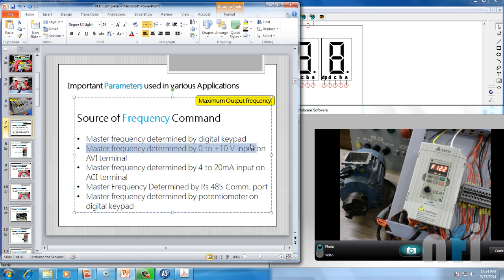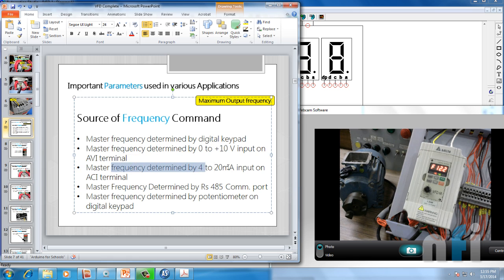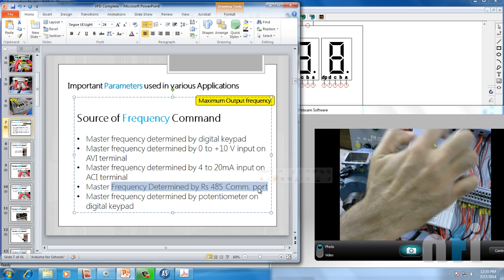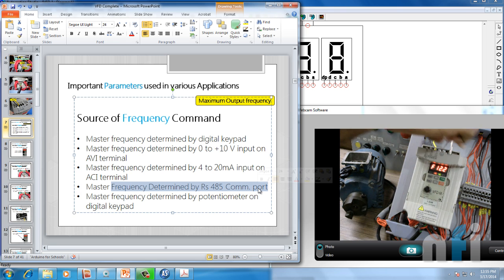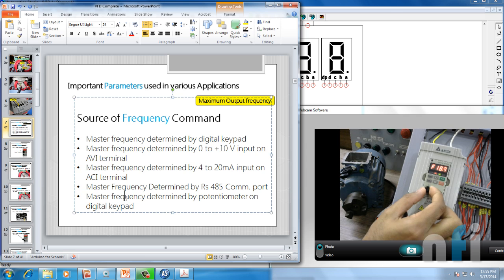The second option says master frequency determined by 0 to 10 volts on AVI terminal — the AVI terminal is over here, so by supplying a voltage of 0 to 10 volts we can control the speed. Third says frequency determined by 4 to 20 mA on ACI terminal. Fourth is master frequency determined by RS485 communication port. The last says master frequency determined by a potentiometer on the digital keypad.